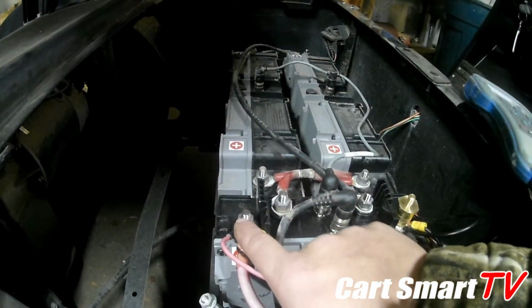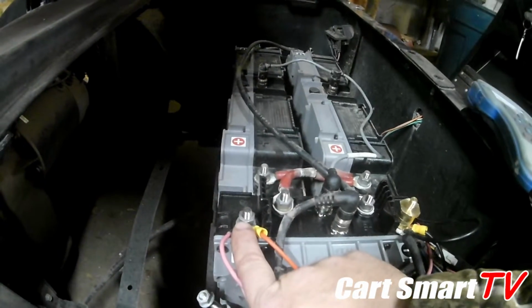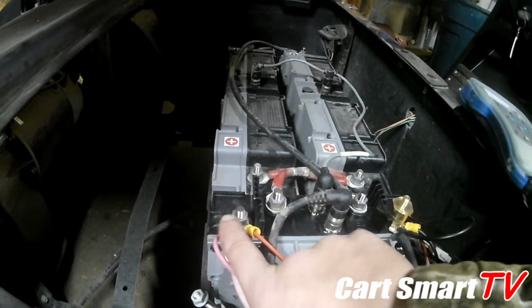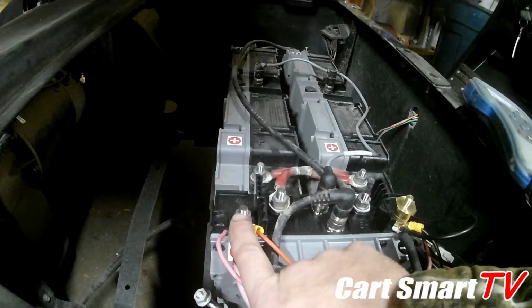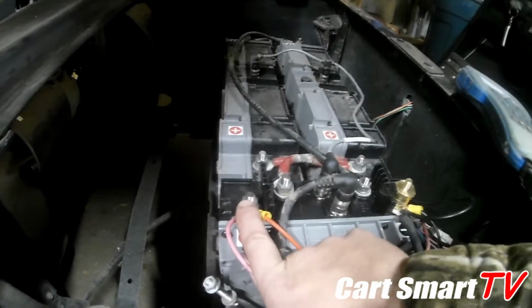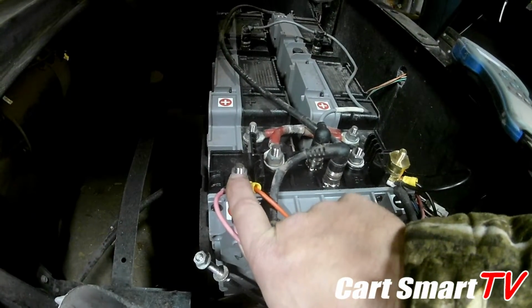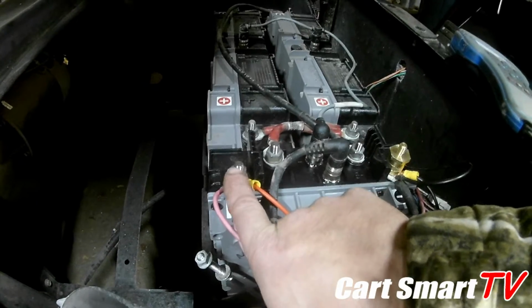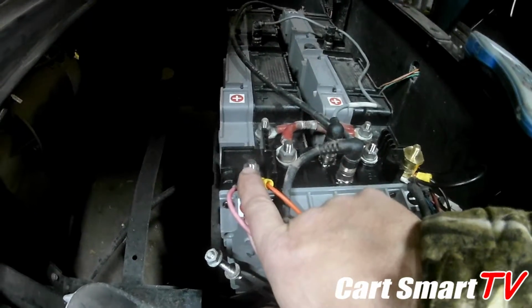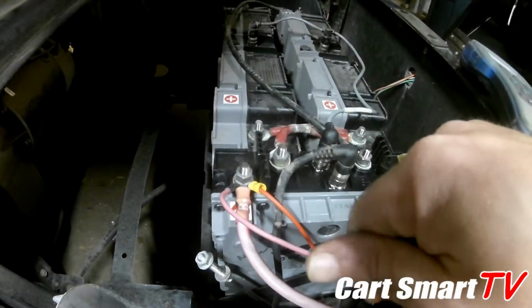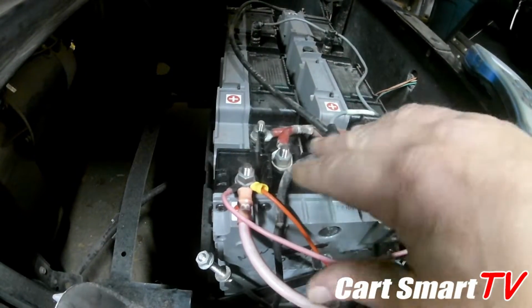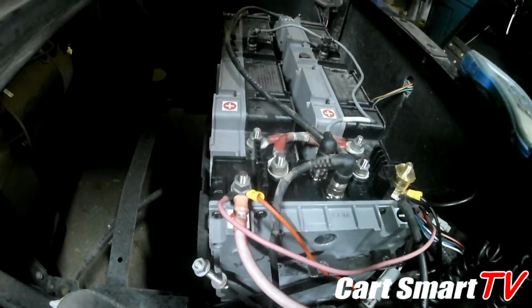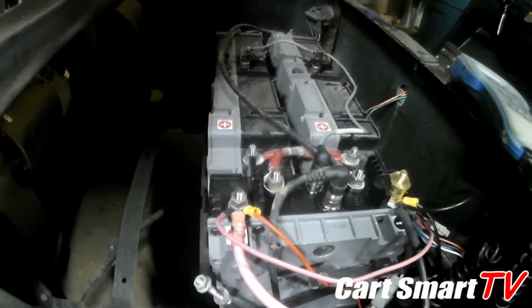Come to find out that when this guy had went to check all these connections, that's why the stud broke off - I guess what had happened was the connection was already loose, and it arc welded itself together, the nut to the stud. When the gentleman went to try to loosen it up and clean it off, he just spun the stud clean off of the old module there.